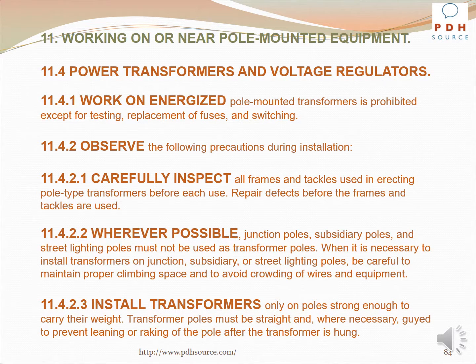With regard to power transformers and voltage regulators, work on energized pole-mounted transformers is prohibited except for testing, replacement of fuses, and switching. Observe the following precautions during installation. Carefully inspect all frames and tackles used in erecting pole-type transformers before each use. Repair defects before the frames and tackles are used.